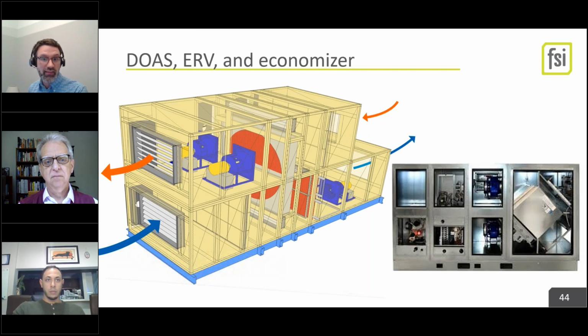Oppose that to the one on the right, and this is more like a lab style energy recovery unit. So that one has a heat recovery core that only does heat, only does sensible for the mechanical engineers in the room. And there is zero leakage between the exhaust airstream and the supply airstream. So if you've got class 3 or 4, like not okay to leak air, you can use this and still get a pretty good heat recovery.